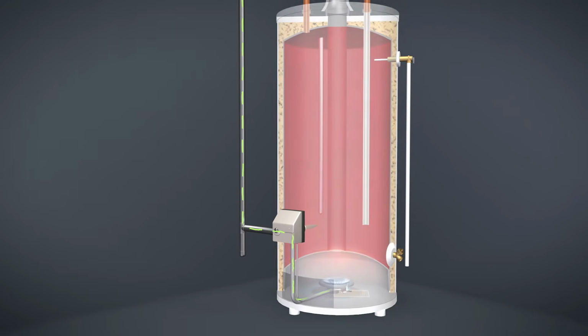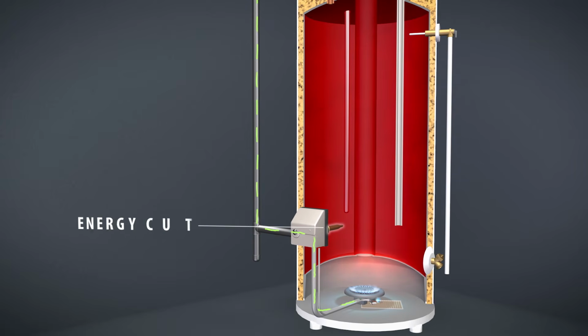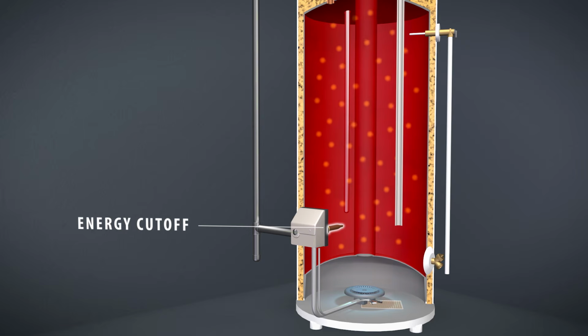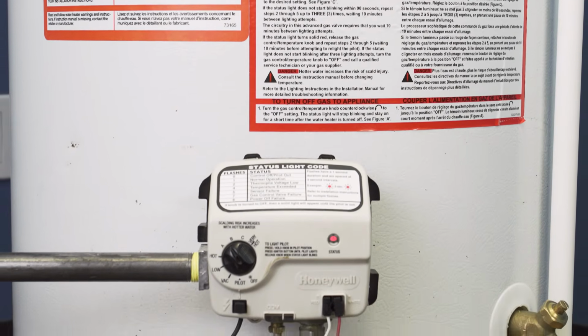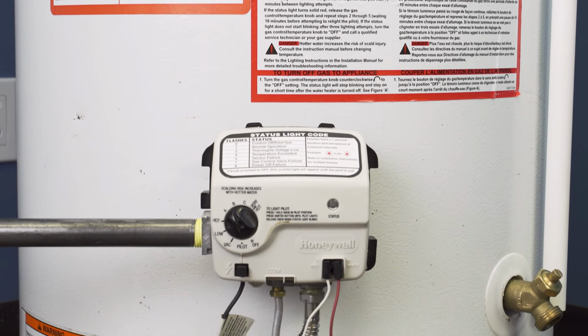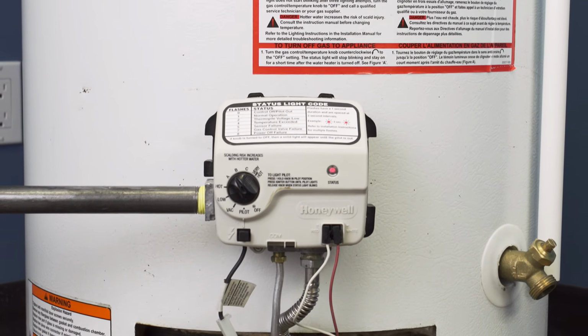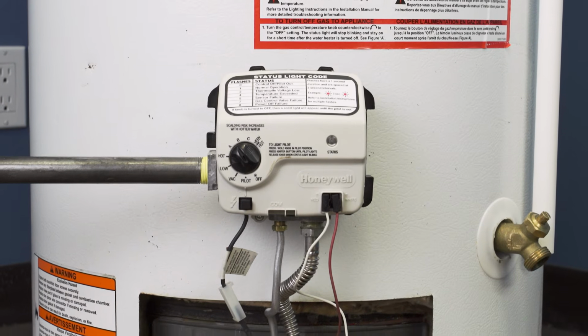Another safety switch is the ECO or energy cutoff. If the temperature inside of the tank gets too high, then the gas valve will shut off. When this happens, you'll likely get an error code the next time you light the pilot. If the energy cutoff is tripped, then you'll have to replace the control valve.